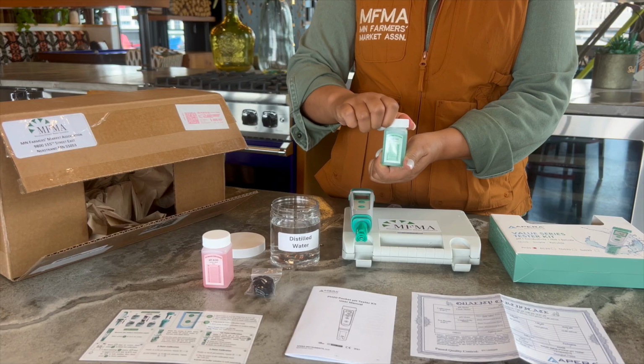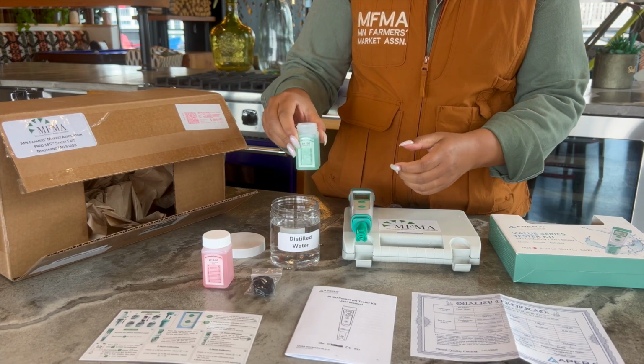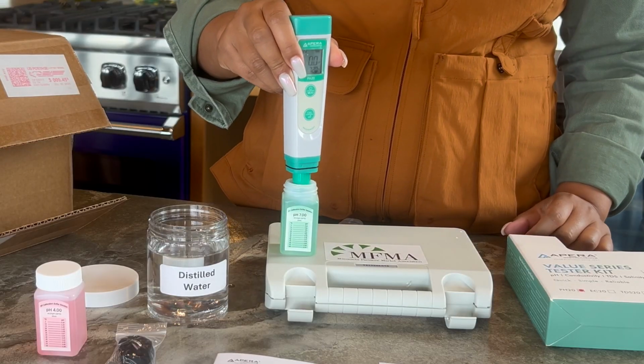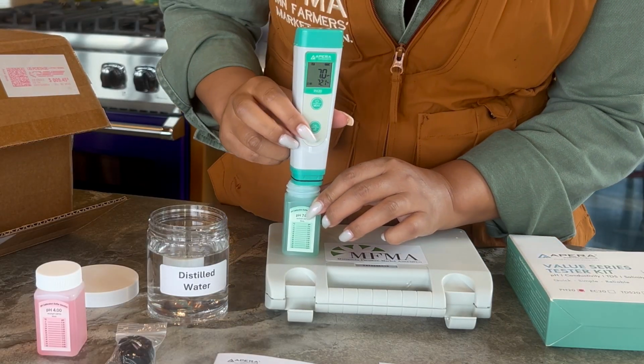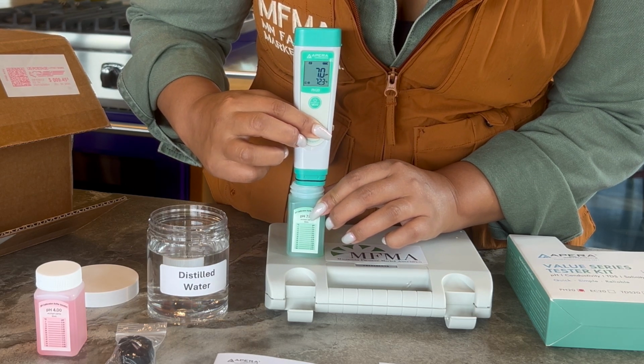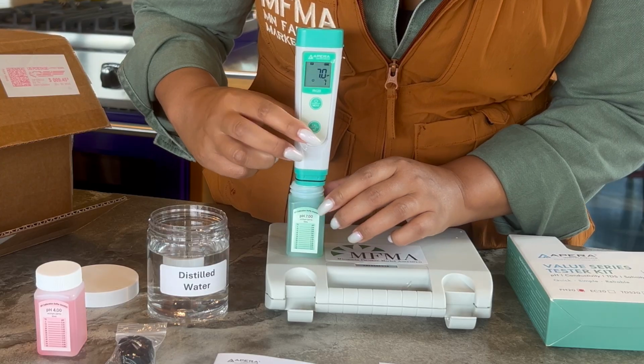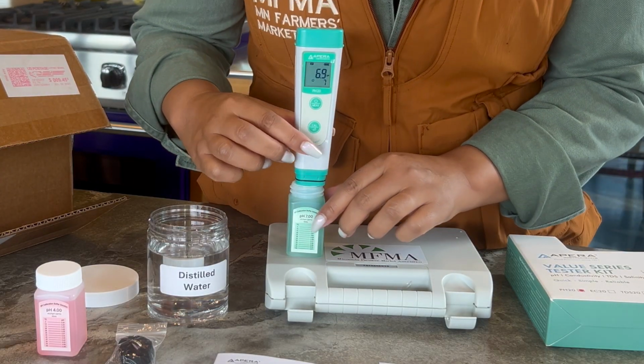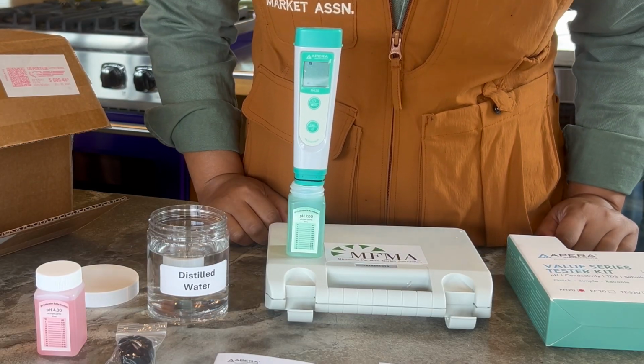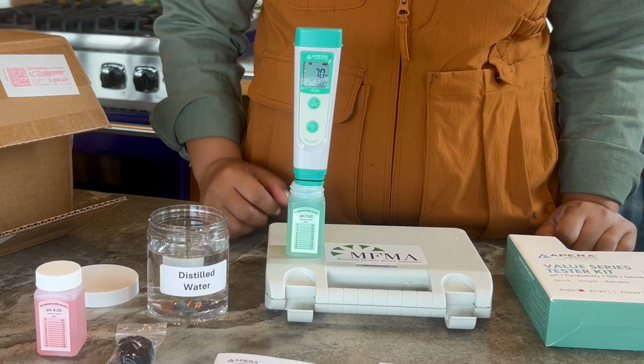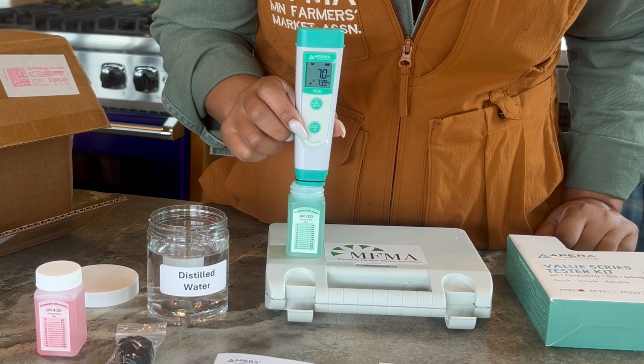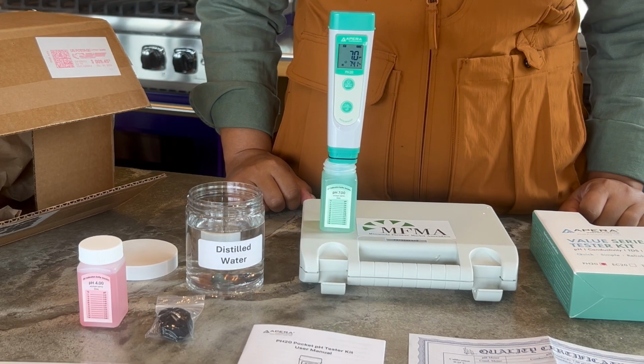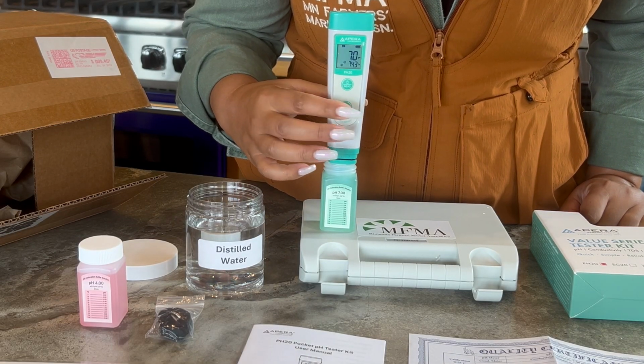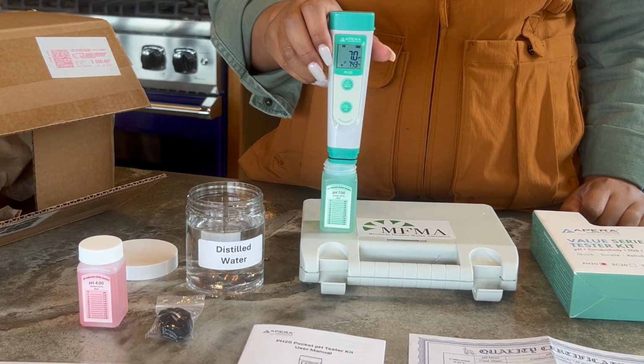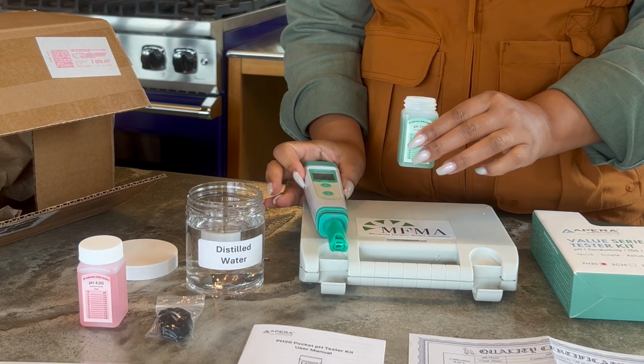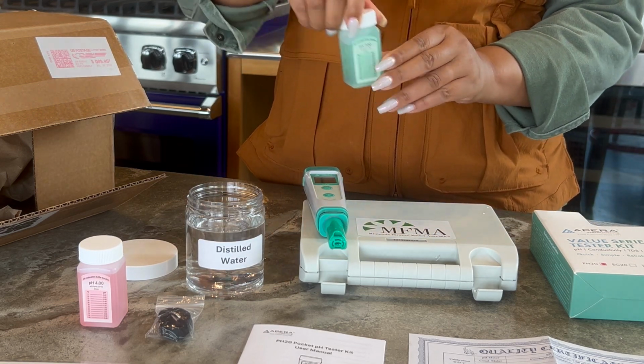Step 3. Open the jar of 7 pH solution, make a quick stir in the solution, then hold still and long press the cal button to enter calibration mode. Wait for the stable reading when the smiley face appears and stays on the screen. Short press to finish the calibration. If you short press the cal button before the smiley face stays on screen, an error code appears. To fix it, wait for the smiley face to fully stabilize, then short press the cal button to finish the calibration. Put the cover back on your pH 7 buffer solution jar.